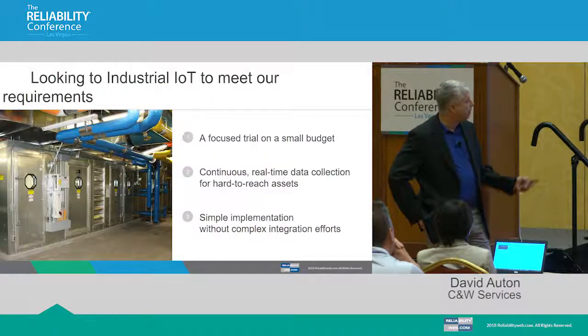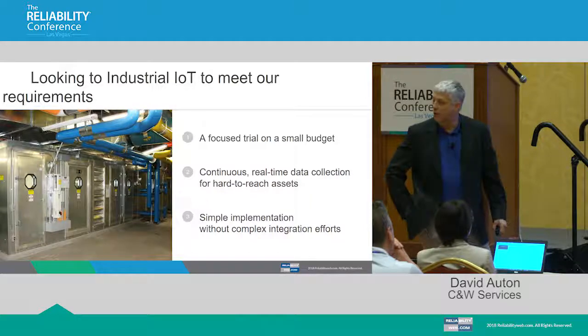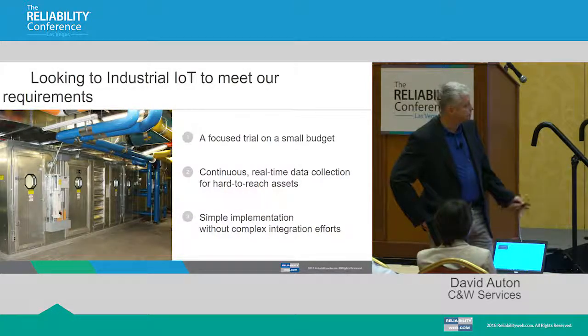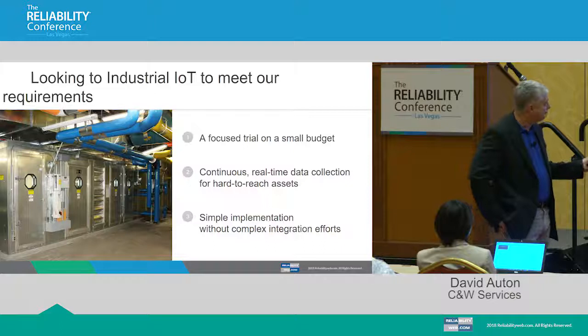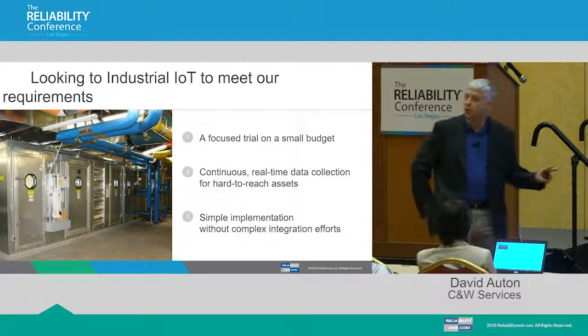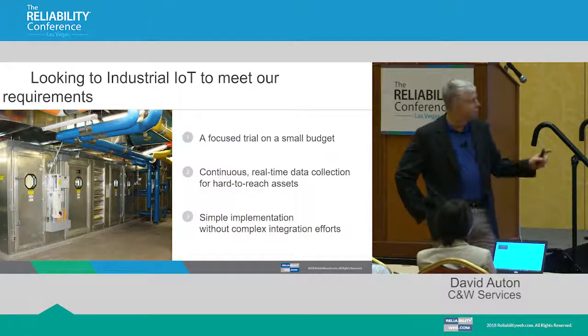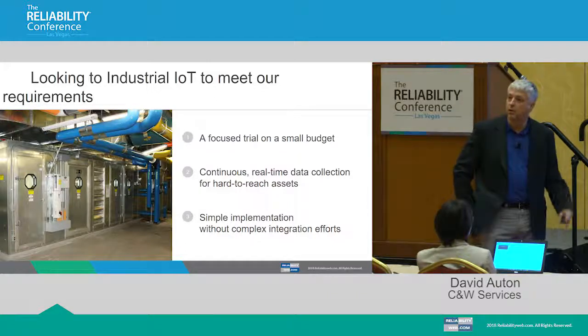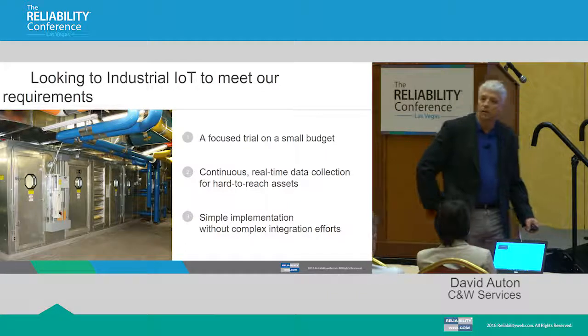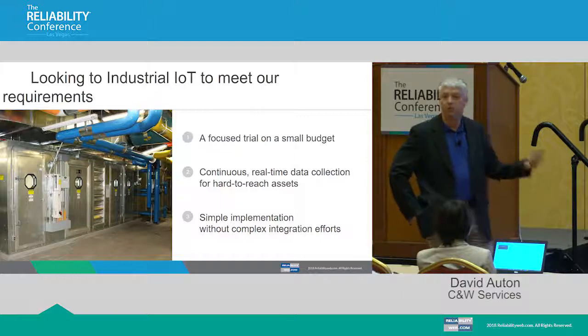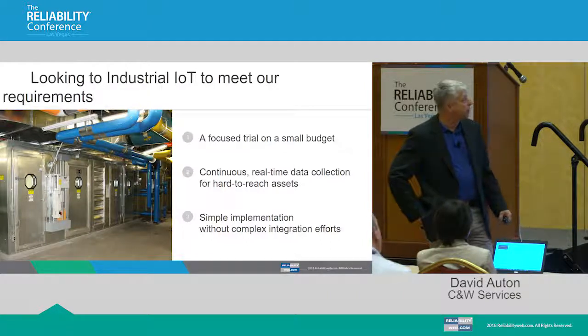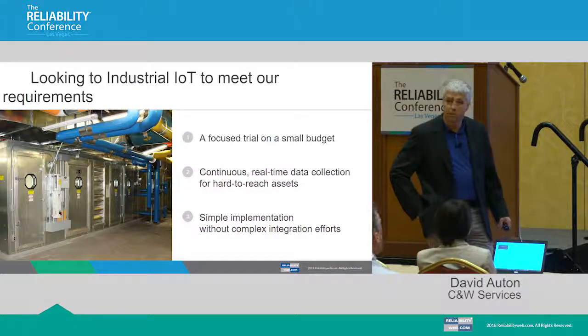And so here's an example of the air handlers, right? They're in a closed case, and so we wanted to at least set up a trial. Will this work? So we identified 6 or 8 systems. Out of the 4 air handlers in one building, we put the monitoring on 2 of them. We put the monitoring on an air compressor system, on a chiller, and on a circulation pump. We really wanted to see how this works. The focus was that we didn't have a lot of money, but we had enough that we could spend $18,000 or $20,000 and get that up and running.